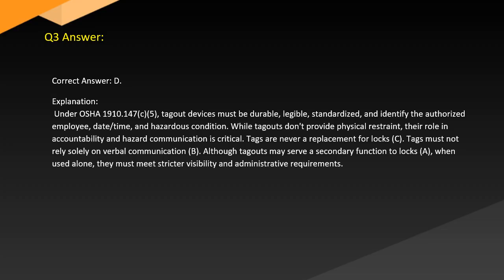Answer. Correct answer: D. Explanation. Under OSHA 1910.147 C5, tagout devices must be durable, legible, standardized, and identify the authorized employee, date, time, and hazardous condition. While tagouts don't provide physical restraint, their role in accountability and hazard communication is critical. Tags are never a replacement for locks. C: Tags must not rely solely on verbal communication. B: Although tagouts may serve a secondary function to locks, A, when used alone, they must meet stricter visibility and administrative requirements.